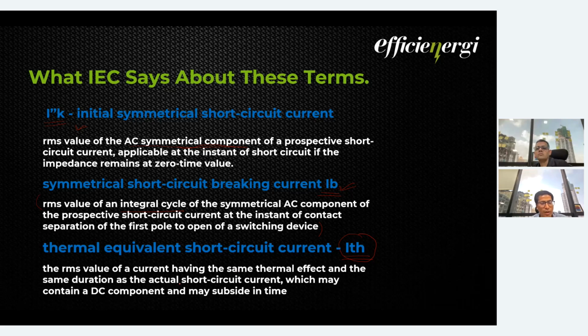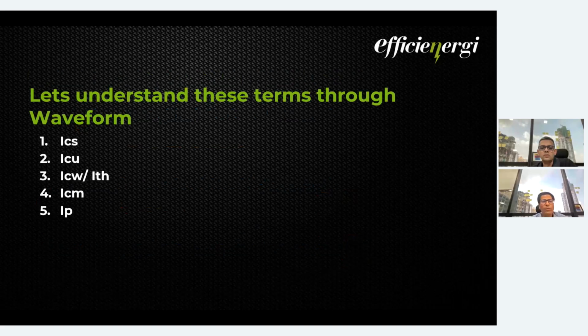But at ECPL, when we carry out the short circuit study, we include this particular component of short circuit current. Again, the name suggests this is thermal equivalent. It depends completely on the I square T capacity of the equipment. Completely thermal. There are no electromechanical stresses that it accounts for.